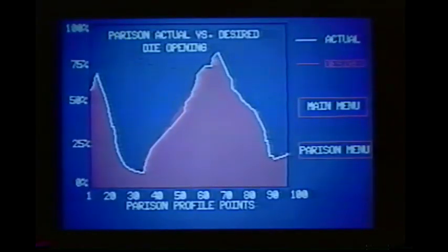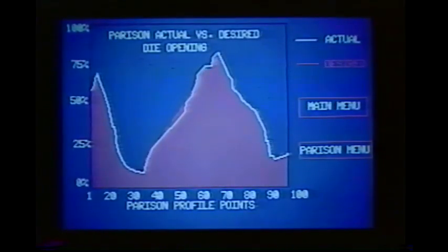So we might even be pulling up a deviation alarm depending on what percentage it's set at. Now a machine operator could look at his bottle approximately at the points 42 to 58 and see if it is causing some fluctuations in his bottle. And he can see exactly where those points are, where his fluctuations are occurring. He can carry this one step further and look at his amplifier card or his hydraulics to see why his tooling is not following his desired position. This is one of the most beneficial screens to a blow molding operator to see his actual versus desired position.